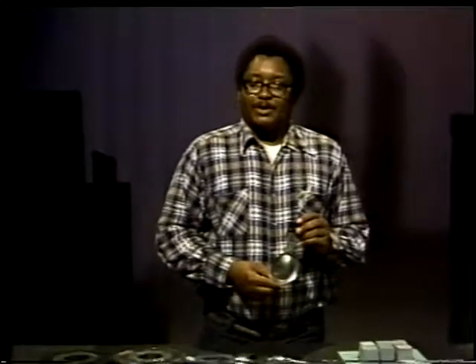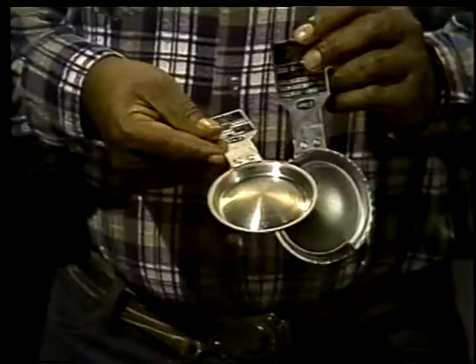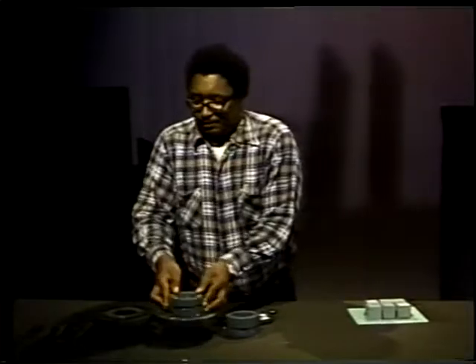If this disc is to be used on a system under vacuum, that is, a system whose internal pressure is below atmospheric pressure, then there's nothing to hold it in place or prevent atmospheric pressure from pushing the disc into the system. So, we use a support device to keep the rupture disc bulging outward. The disc and support fit into a holder, which is bolted in place between two flanges.